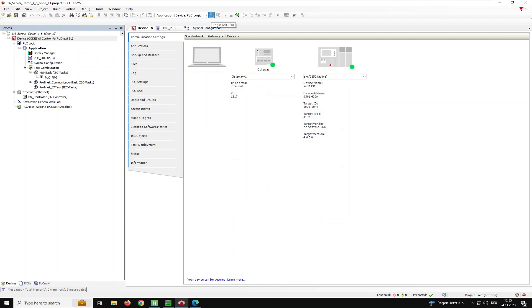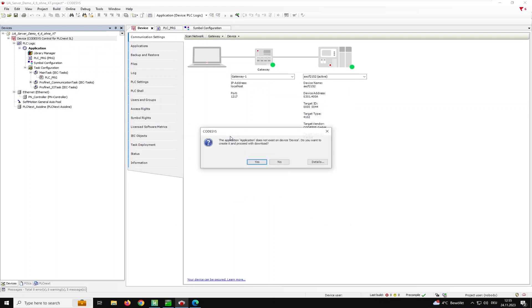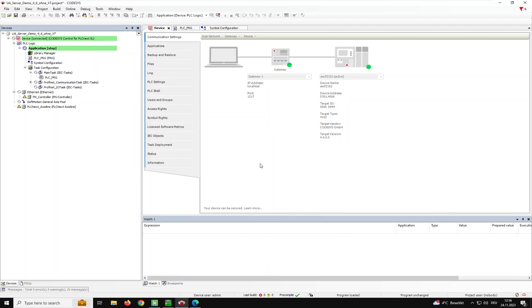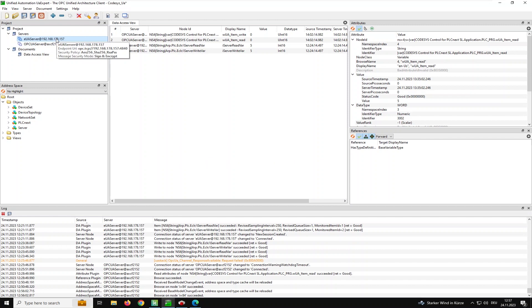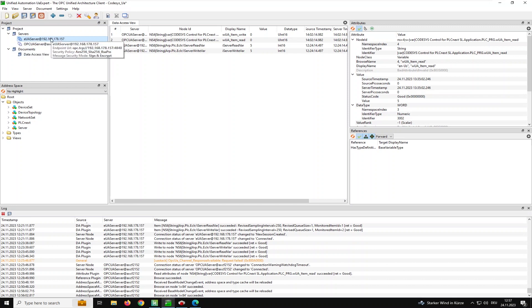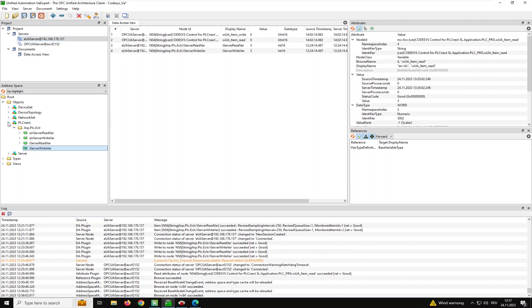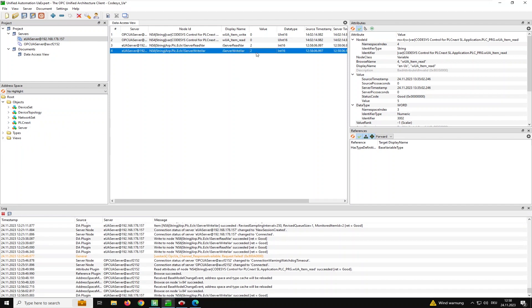You can now deploy this application to the PLC and start the application — the system is running. Let's check if the OPC UA items are available and switch to the OPC UA expert test client. The server shown is the PLCnext control, the initial controller in the project. Both variables are coming from the server and are available. If I send a value to the write variable, it's copied to the read variable.